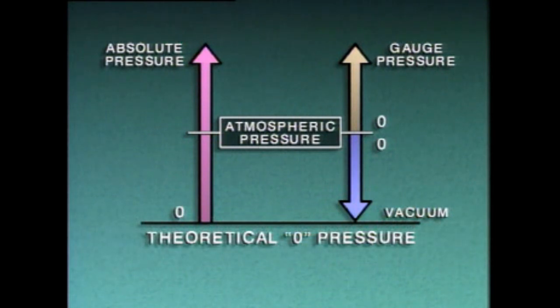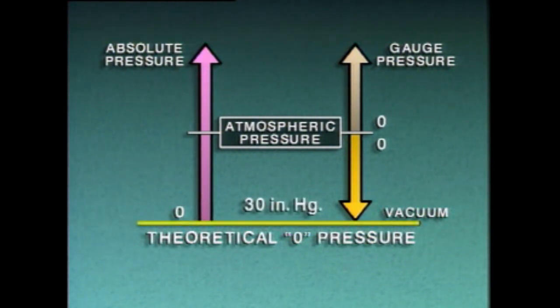If theoretical zero pressure, or a condition of perfect vacuum, could be reached, it would have a value of approximately 30 inches of mercury vacuum. A number of different devices can be used to measure pressure. One of the most basic pressure measuring devices is a manometer. A manometer operates on the principle that a column of liquid of a certain height will always exert a specific amount of pressure.